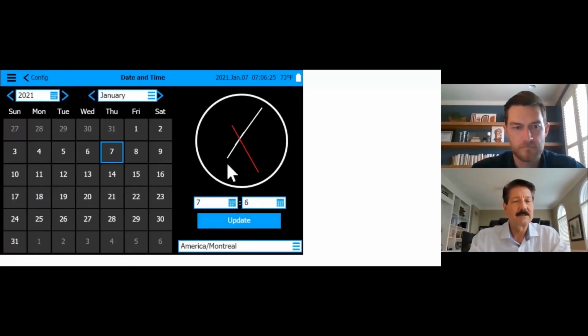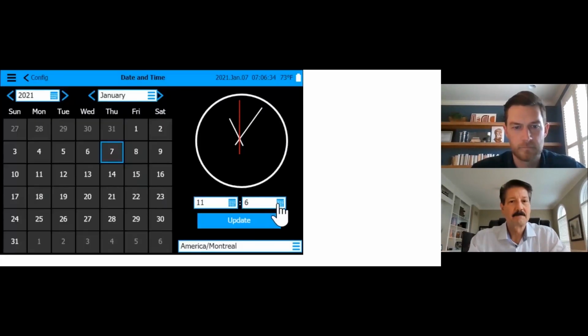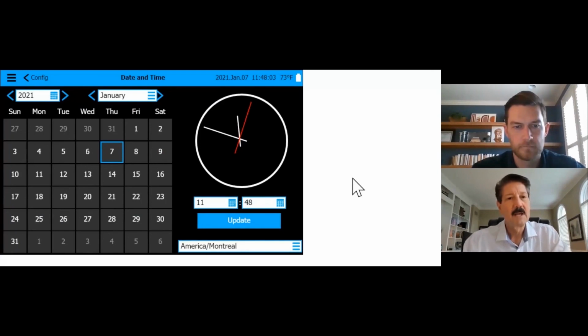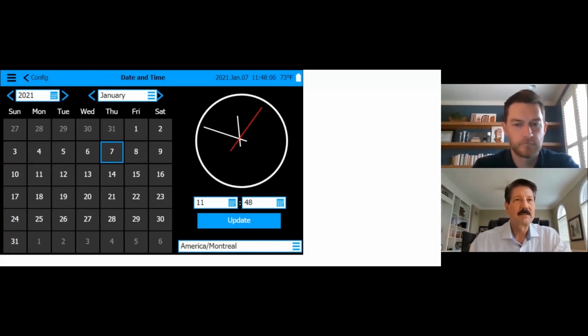Date and time, let's get into that. So we're showing today's date. We're showing the time. What is the time here? We got 11. Okay, so updated the time, but any logs, this is something that they'll do at commissioning, is update the time also, because any logs that are documented in the memory will lock into that date stamp. And if it's incorrect, then that's exactly what you're going to see in the data that you're going to be viewing. So I just corrected this to 11:48, and again, this is exactly what we're going to see.